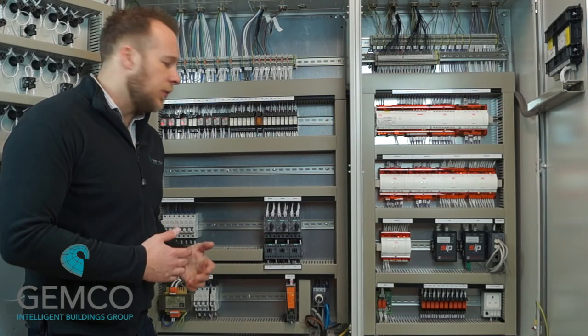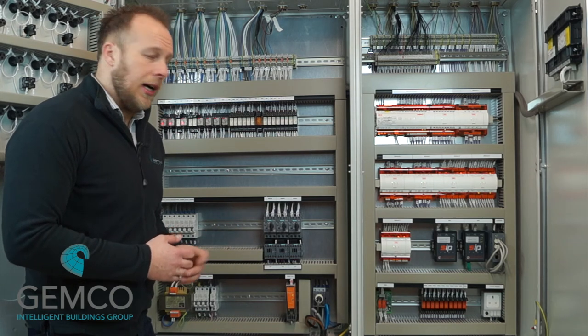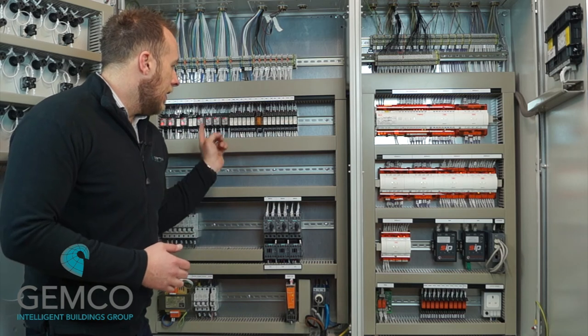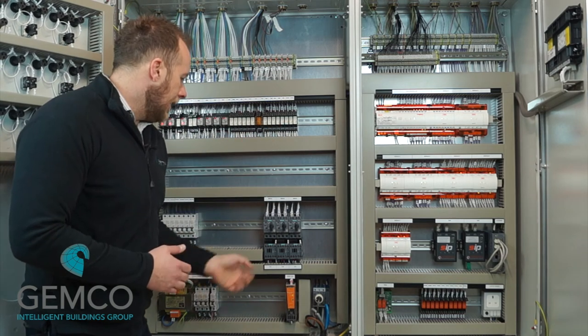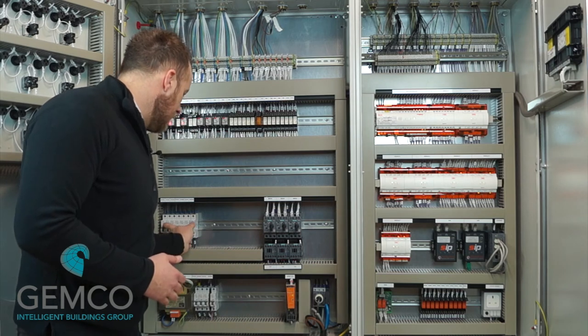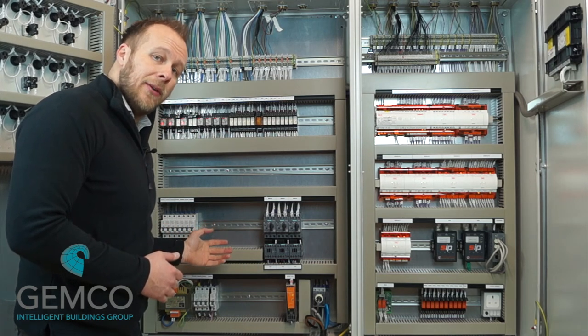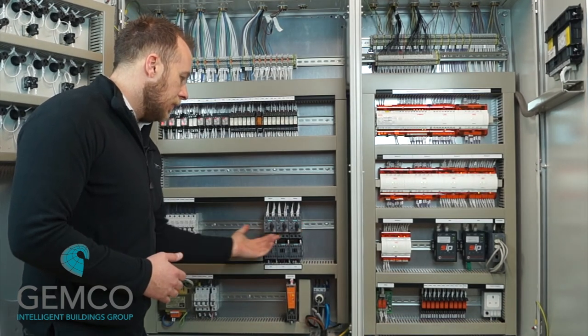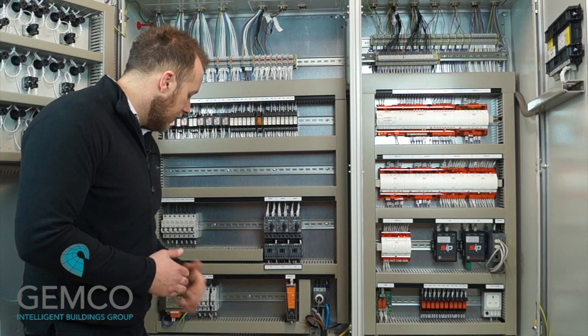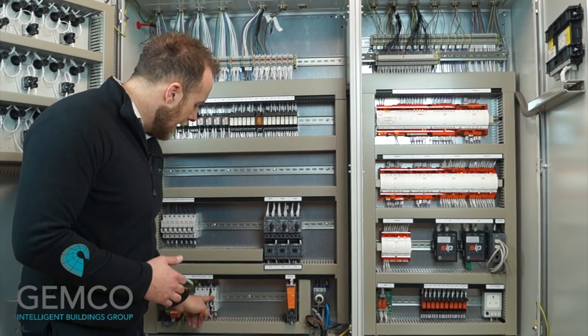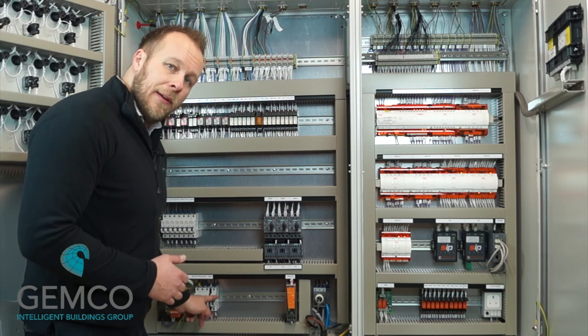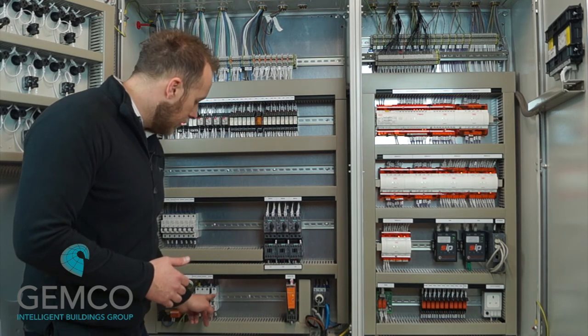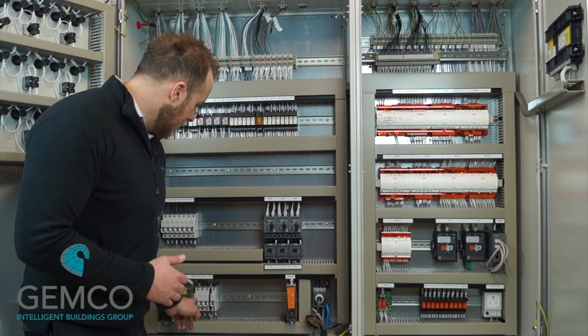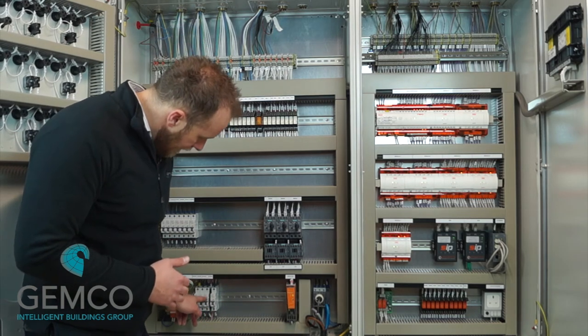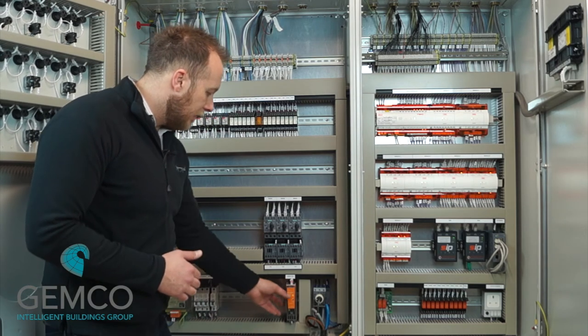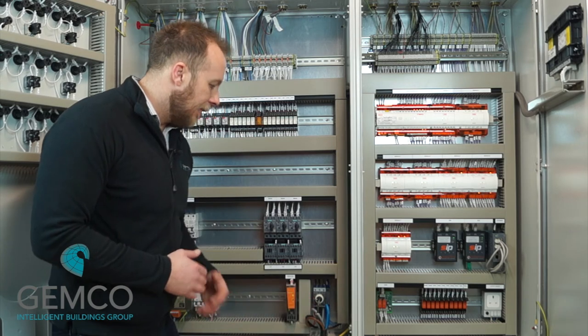Alright, so this is the power section which I just went over. I just want to show you inside to show you what it looks like. You have your incoming terminals up here, a bank of relays which do all the monitoring, and then we've got the power section which has the MCBs which just look like what you would have in your house, and these are manual motor starters which start the pumps and any motors on the system. Down here you have the transformer and the control circuit MCBs and fuses. So if the control circuit live lamp has gone out, that'll be because MCB 2C has tripped. Okay, and then obviously we have a mains incoming isolator here which will shut the panel down.